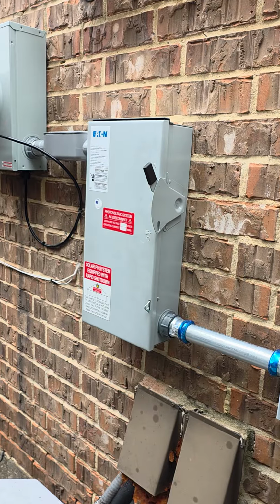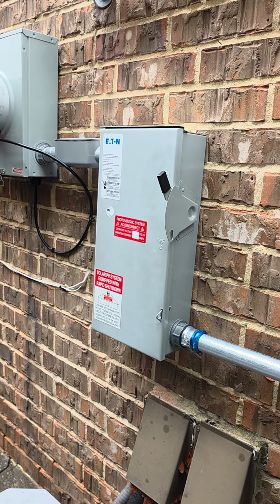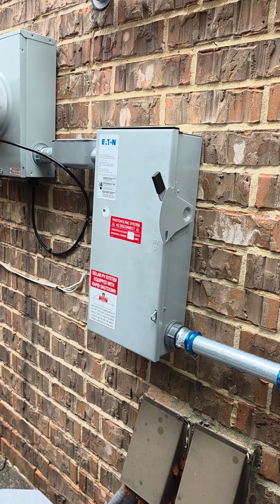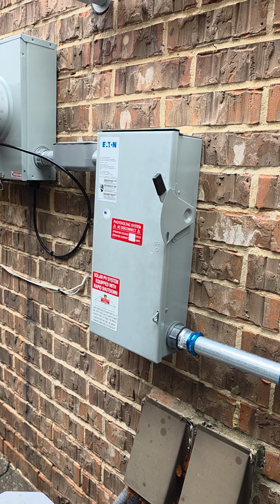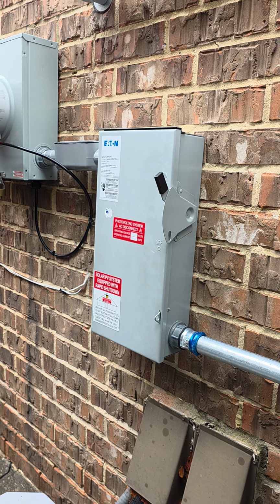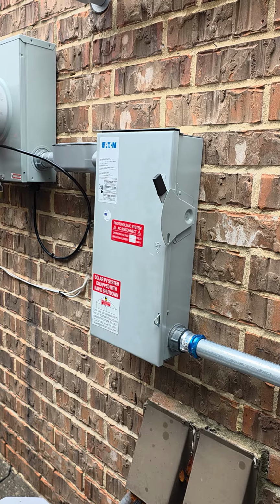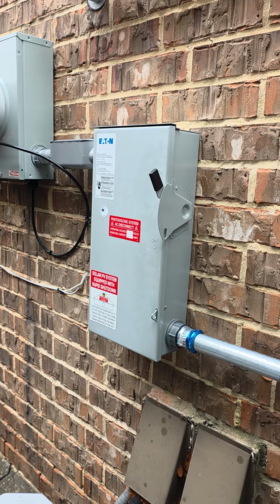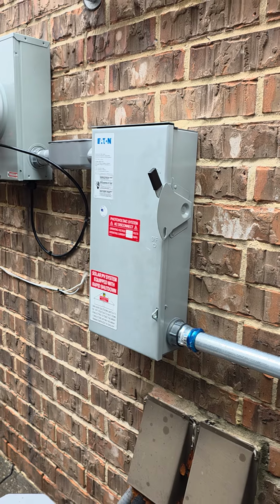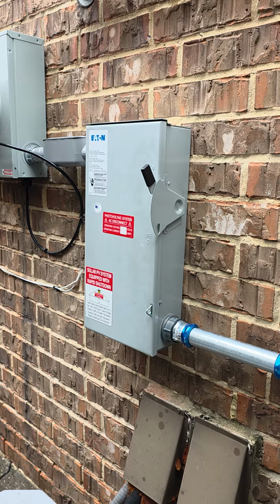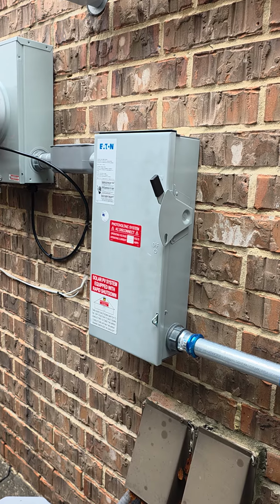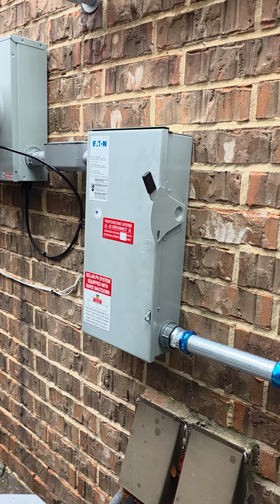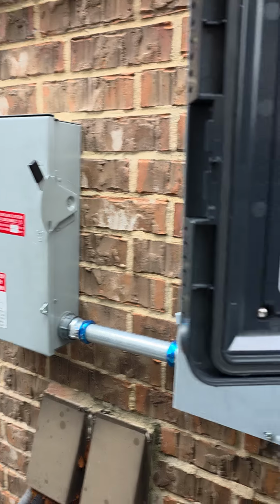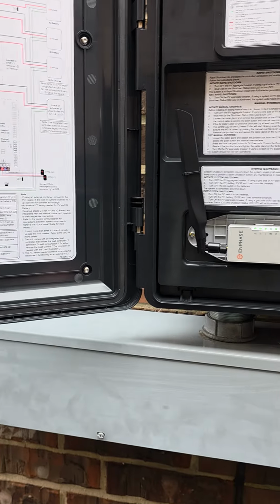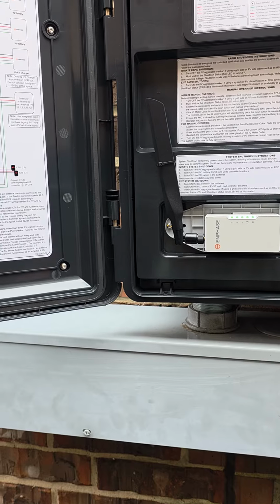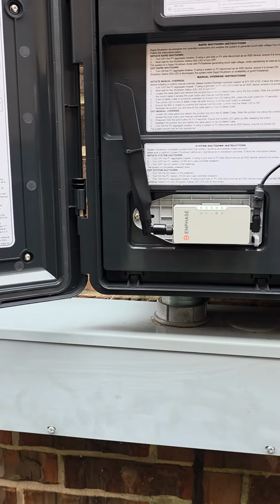I ended up using lugs at the main panel and connected straight to the mains going into my main panel, and didn't use a backfeed breaker. And in my scenario, I have a 200 amp panel and 150 amp breaker. So my backfeed limit is 90 amps. And I wanted to utilize all 100 amps. I know it's kind of silly for 10 amps, but I wanted to use the maximum backfeed capability of the system. So I actually tied into the main lines going into my main breaker with lugs, just so there's no circuit breaker limit. And also, if you do the 120% rule for the breaker, then I don't know, maybe my limits would have been even worse.